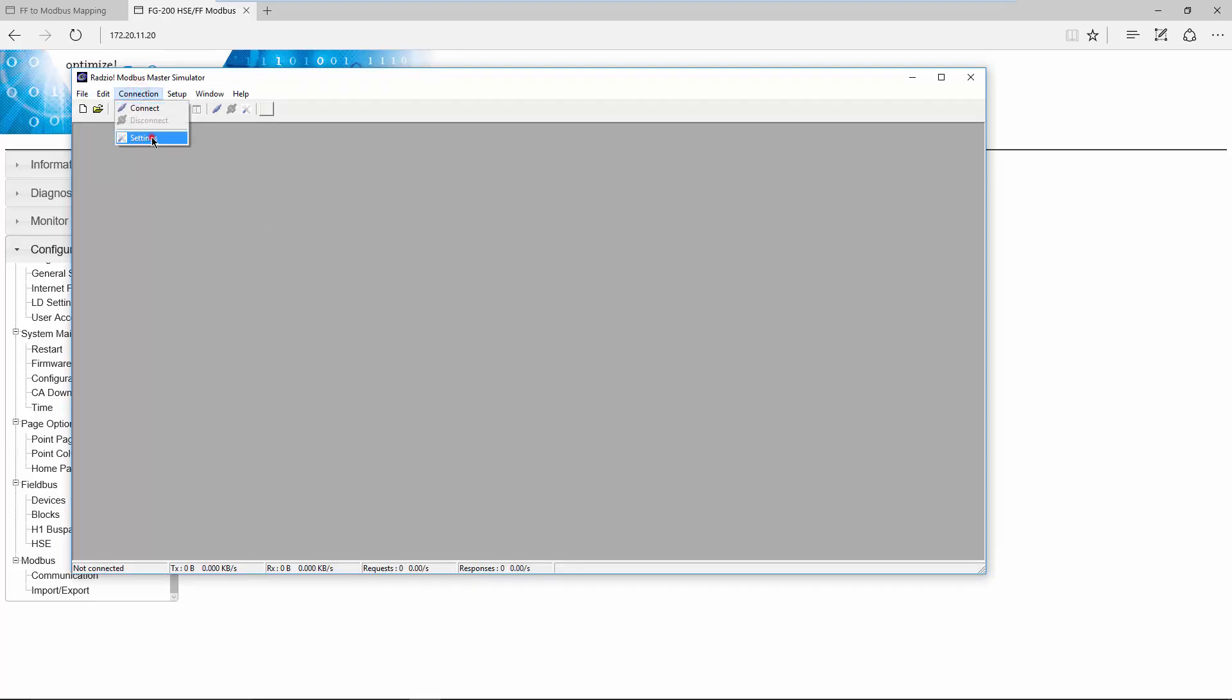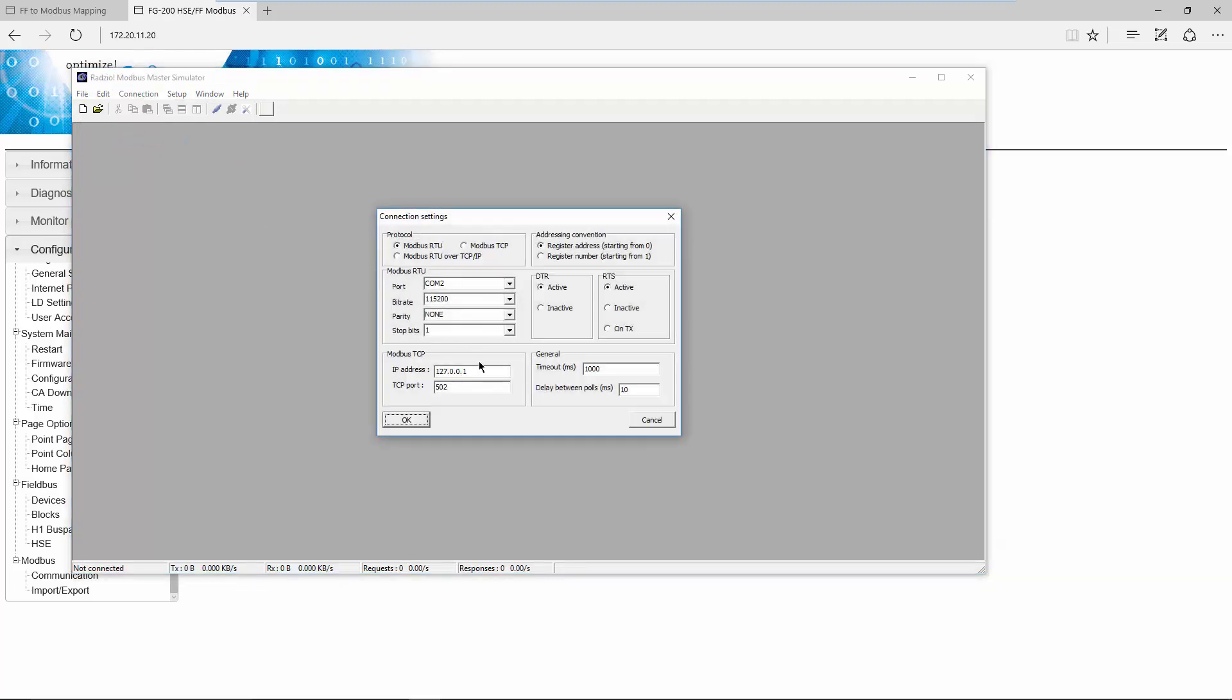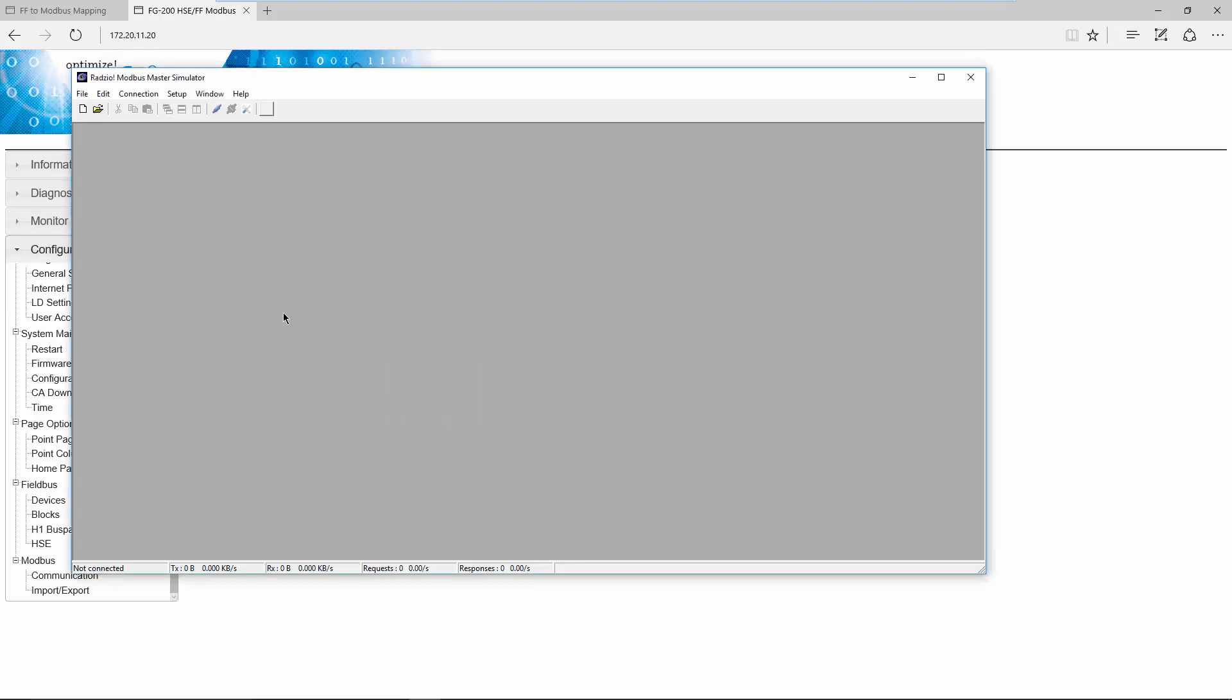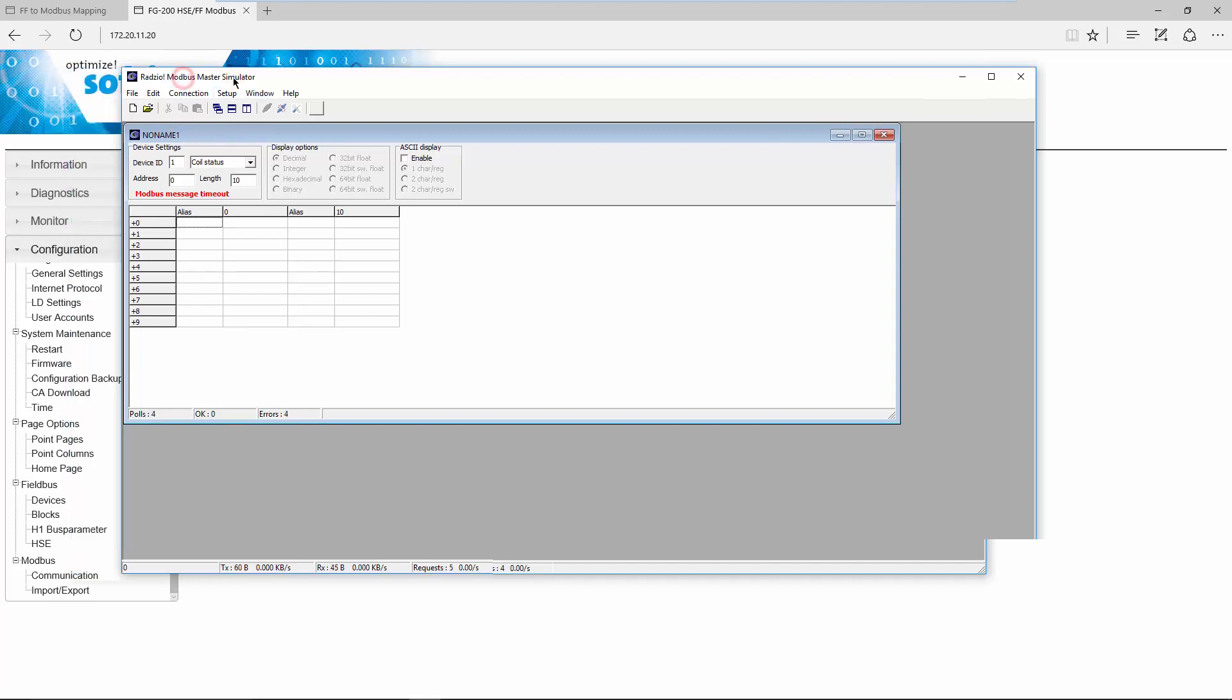To establish a connection, you have to select Modbus TCP as protocol and you have to define the IP address of the FG200. Per default, the port 502 is used for the Modbus communication. This can be changed on the Modbus settings of the FG200. Click on the symbol to establish a connection to the FG200. Click on the symbol to open a window to read out Modbus register.